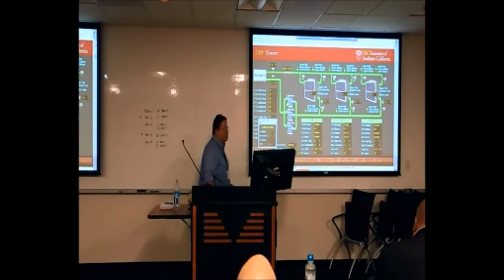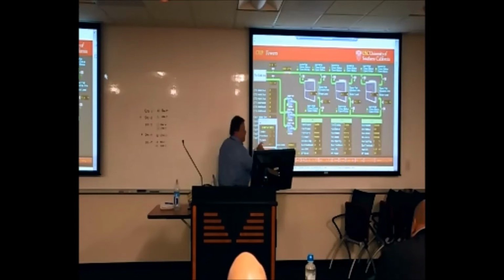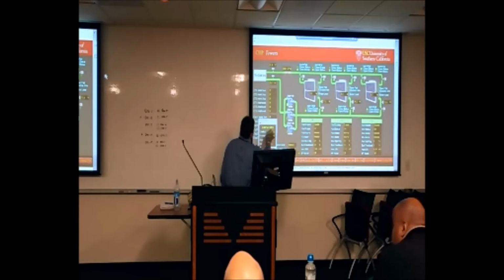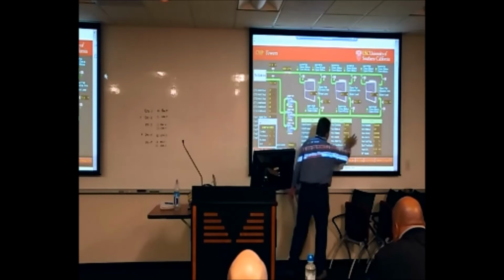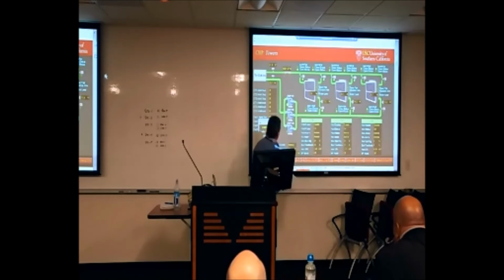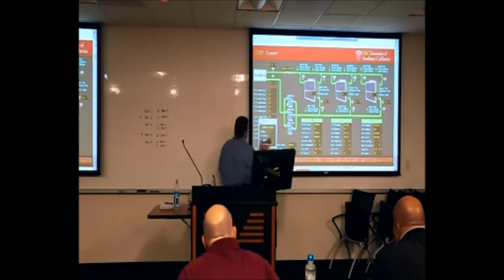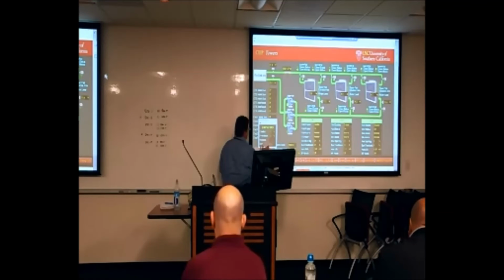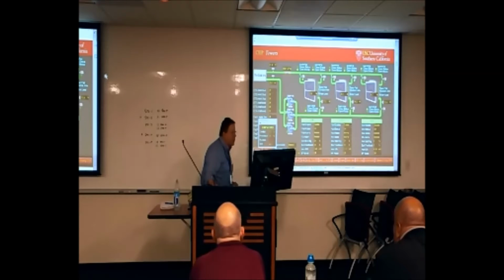Here's the information on the variable speed drives. I guess we didn't get the bypass point programmed. I'll have to check this, George. So we have this data listed right here. It was as listed already for the tower, so that's just modified new point data. This one here, if you click on each one of the pumps, is how we reflect the pump data. So we do see the pump status by virtue of the impeller turning. The pump command is a green light right there. The control speed is 75%. The feedback is 76. The KW is 40. Somehow the bypass missed getting programmed, it would appear. So we'll put that on the list. For each one of those it did, so okay.